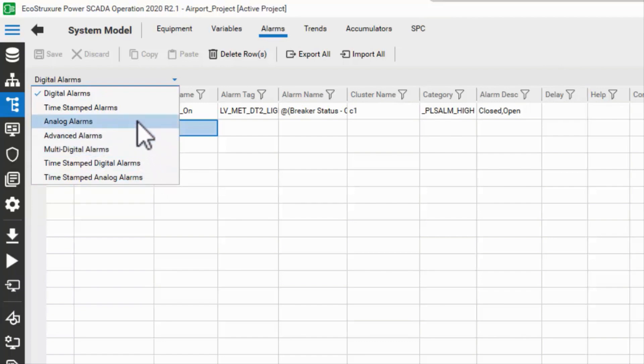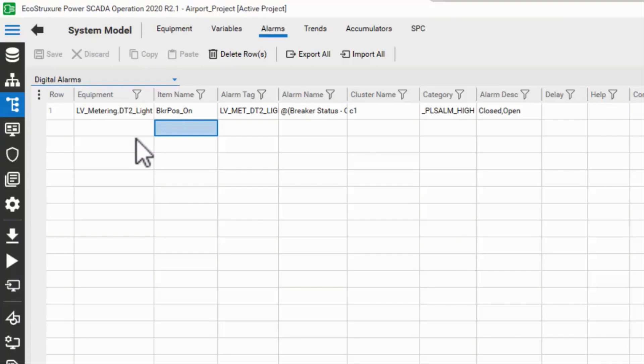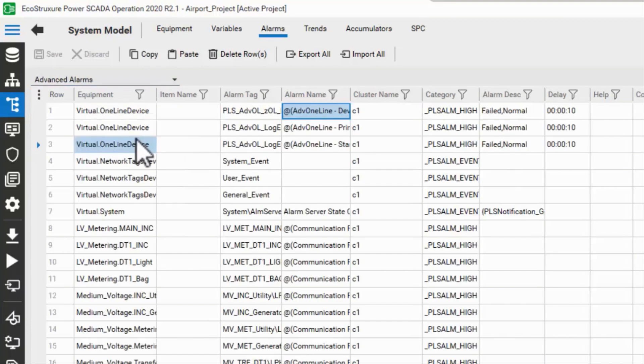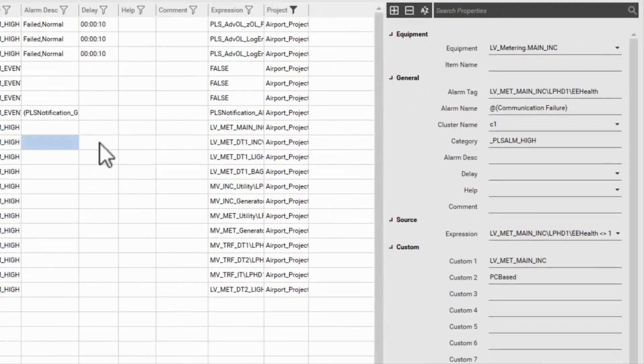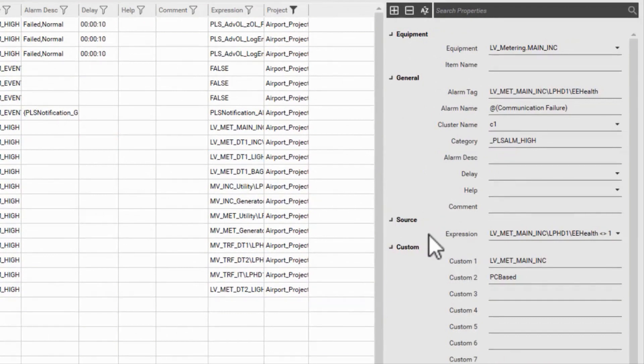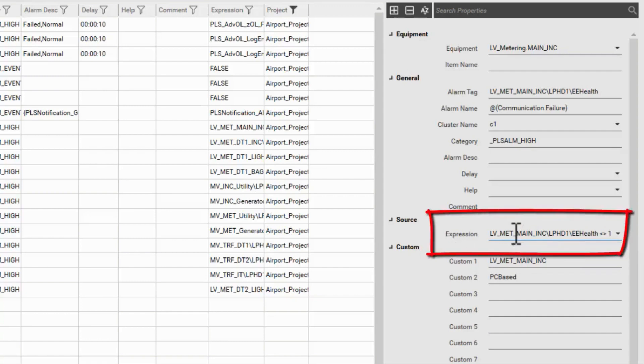Next, we have advanced alarms, which are the last type actually generated by the profile editor in one special case. An advanced alarm is populated in much the same way as a digital alarm, with one exception: instead of one or two digital tags driving the alarm, we have an expression field.